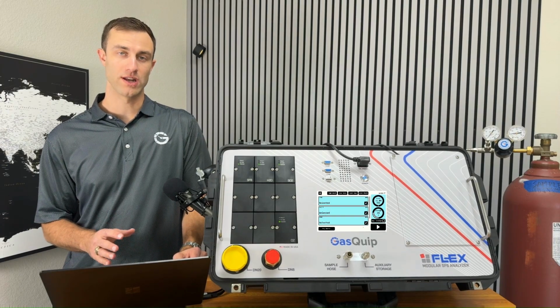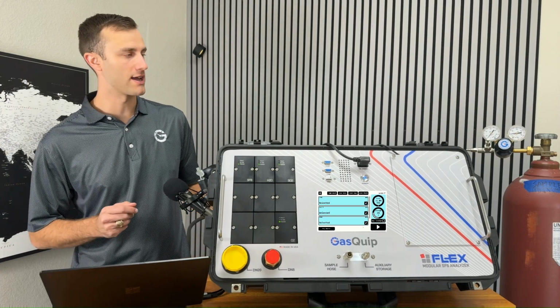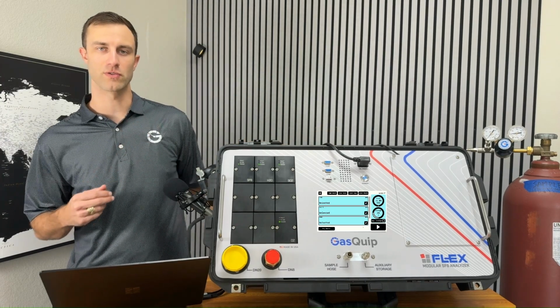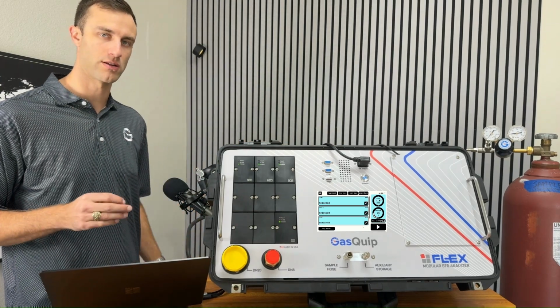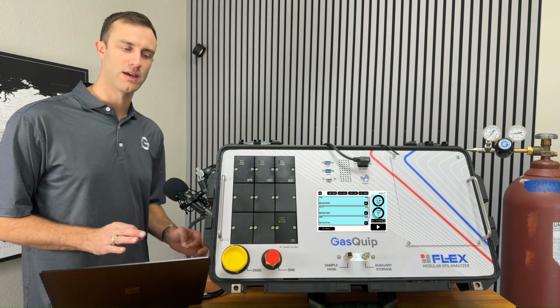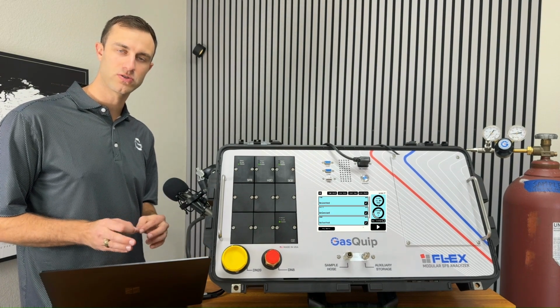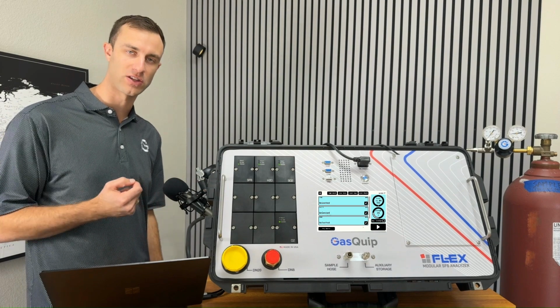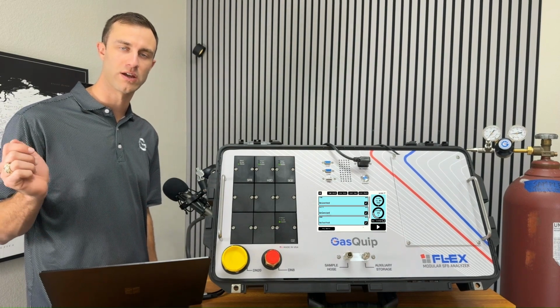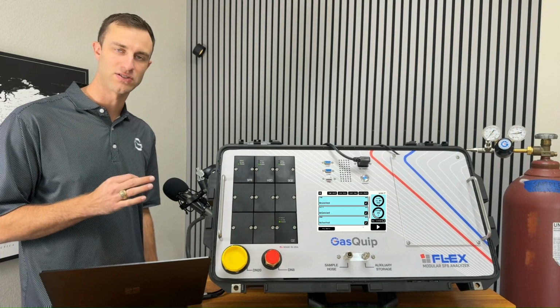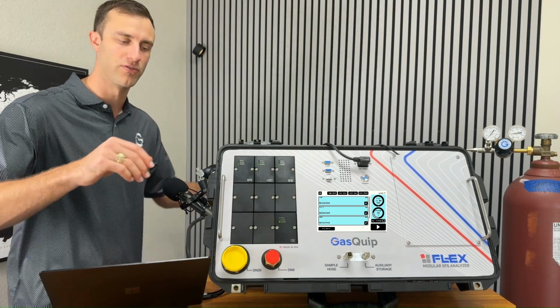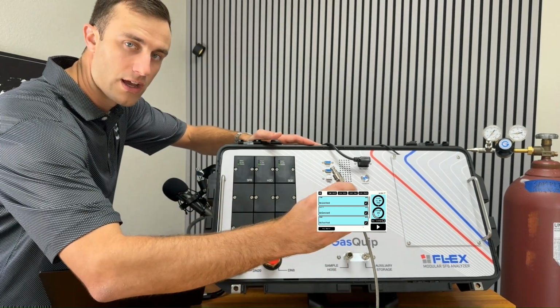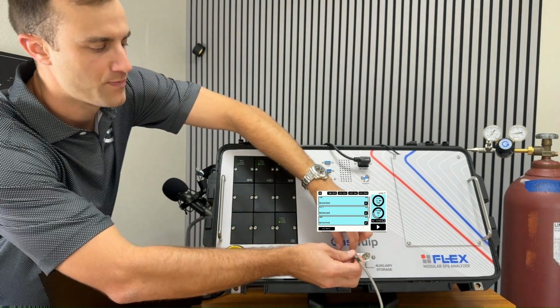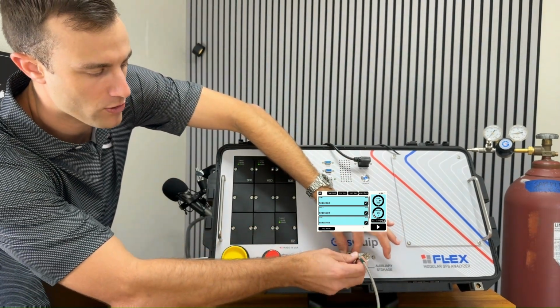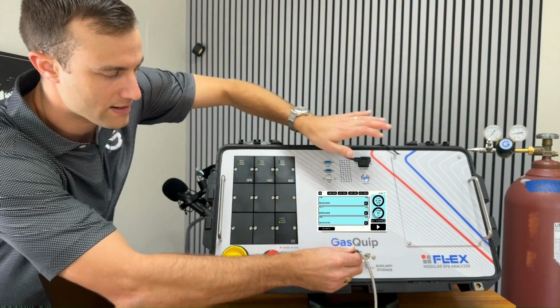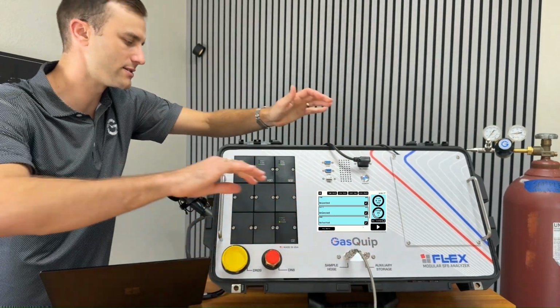Now we're ready to run an actual test. So I've got a pure bottle of SF6 over there, and I've got our sample hose down here. The first step is going to be to attach your sample hose to your analyzer and pull an evacuation on the hose in order to get rid of any prior tests or sample of gas that was in there before we started. So we'll take the male end of our hose and connect it to the female sample hose port, pull back the collar and then connect up, and you'll hear it click when it's connected.